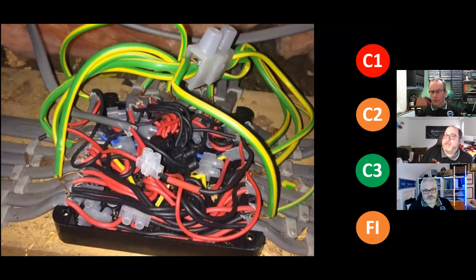What is this? It's a mess. It's another loft special, isn't it, really? It's not one of mine, but I would put C2 on that, because there's all those connectors just exposed. So C2 is a minimum. And there's no way you're going to get the lid on, although the cables are quite nicely clipped on the sides. Someone's put effort into that, but then realised when they were doing it that there was no way. This is the beauty of Wagos. Wagos could fix that mess.